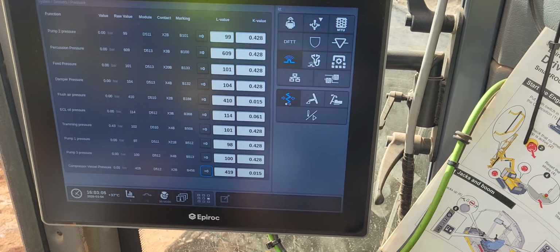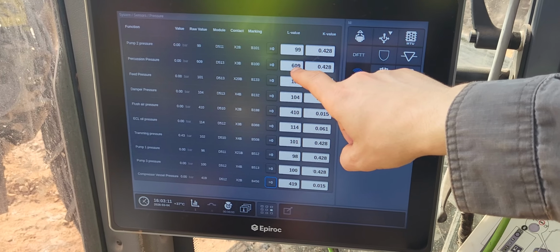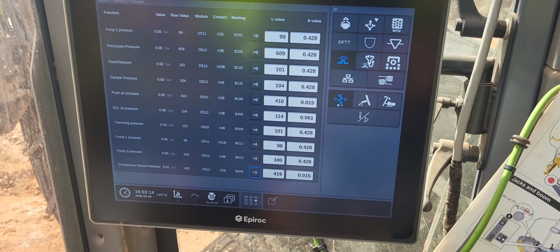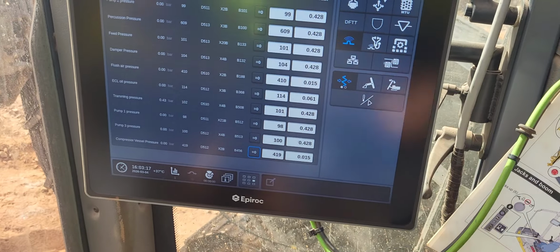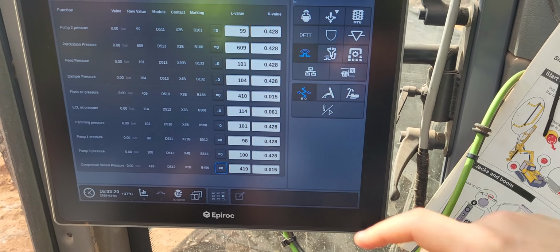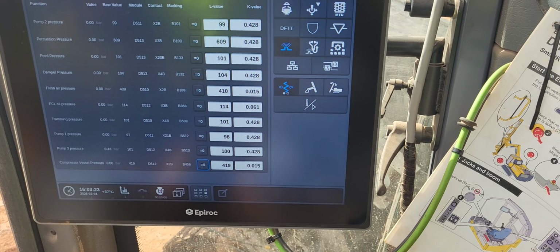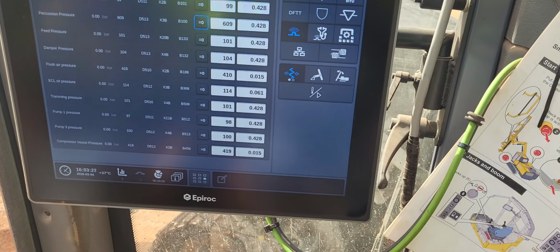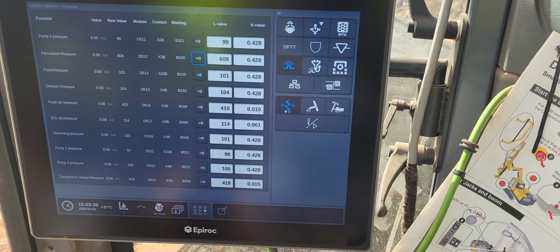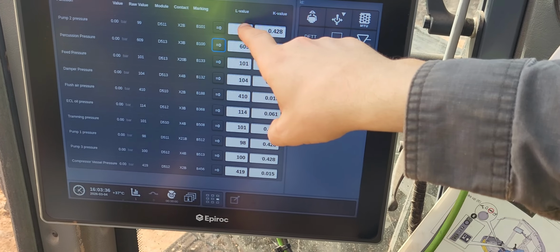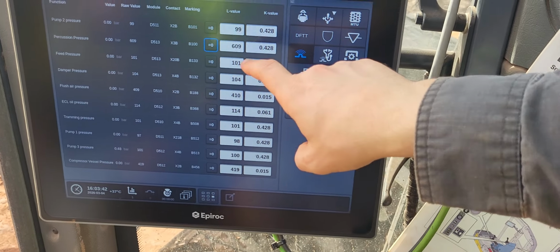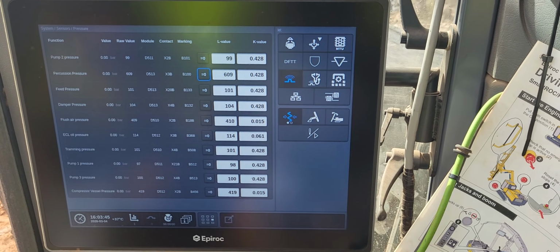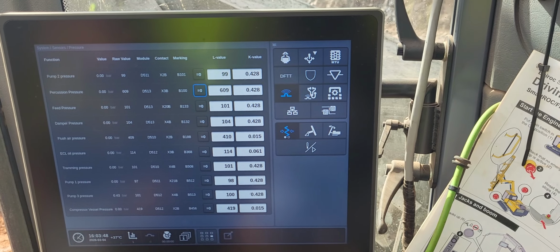Good. Here, for example, we see that one of the sensors is broken. Why? Because the low value doesn't correspond to a standard one. Okay. You can see the pump 2 pressure is the same type of sensor as the percussion. So it's 0 to 350. And if you, for example, when you reset it, see a low value going very high, like 600, you see that all the 0 to 350 bar sensors have the low value, the L value, around 99, 100, 104. But this one is different. So it means that the sensor is broken.